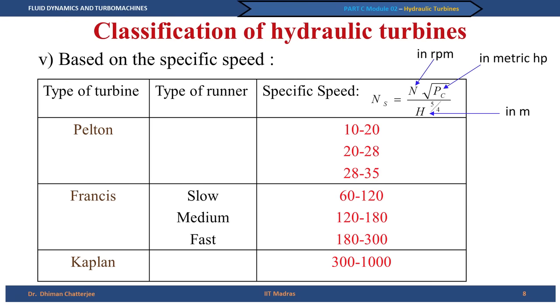The definition of specific speed N_s is given as N√P_C divided by H^(5/4). Note that it is H to the power 5/4 here, whereas for pumps in the last class we used H to the power 3/4. The coupling power P_C is in metric horsepower, N is in RPM, and H is in meters.